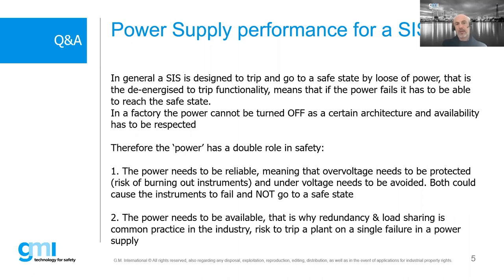So the power needs to be reliable. The overvoltage has to protect from the risk of burning the instruments. And also the undervoltage has to be avoided. Both cases, high voltage and low voltage, could cause the instrument to fail, not to go to a safe state. The second role is that the power needs to be available. And that's why redundancy and load sharing are very important in the industry. So if you have a power that goes down, everything goes down. You fail with the power, everything goes down.